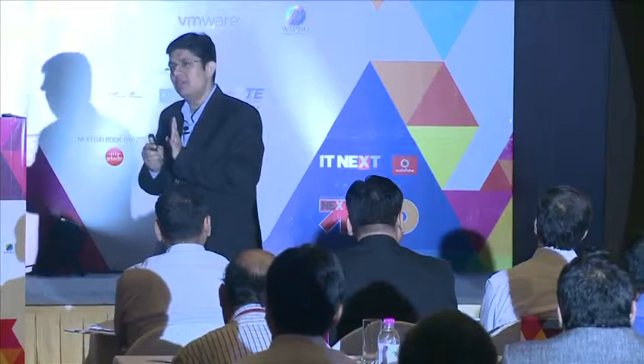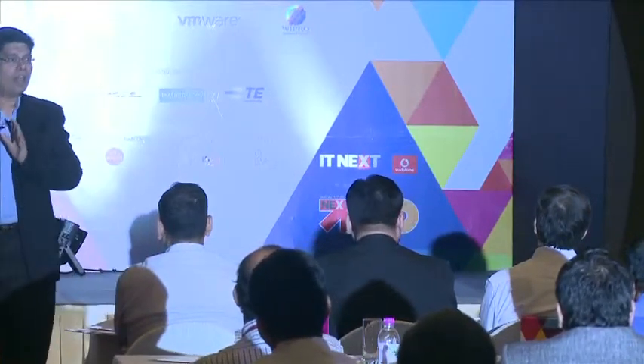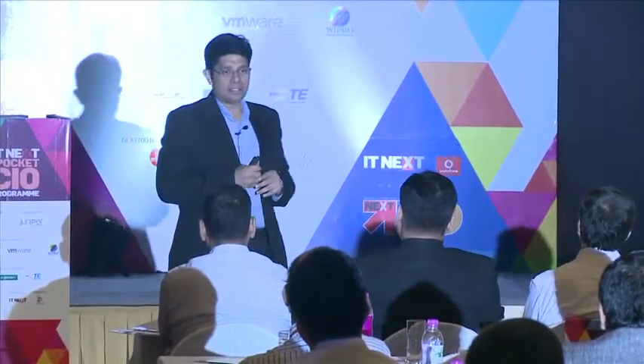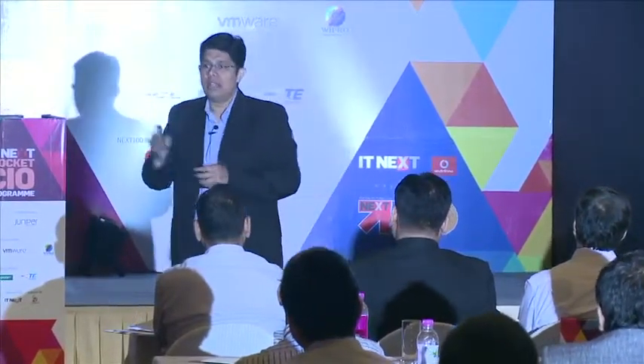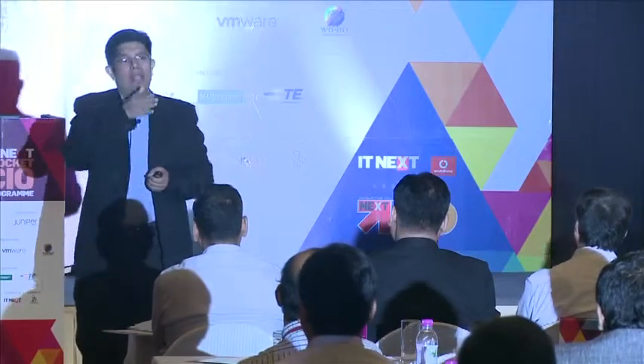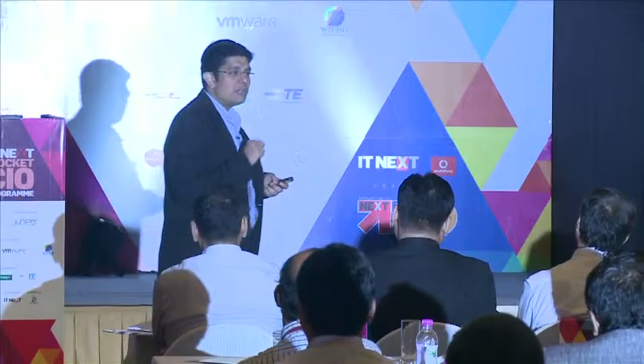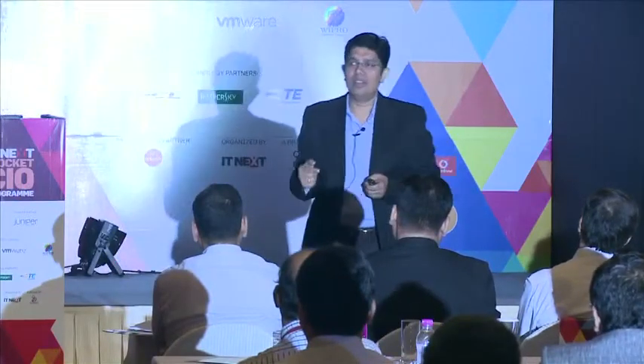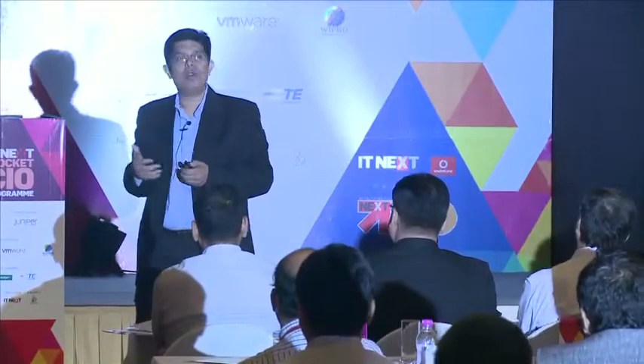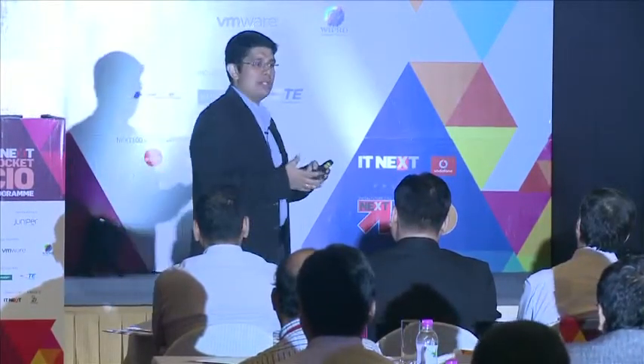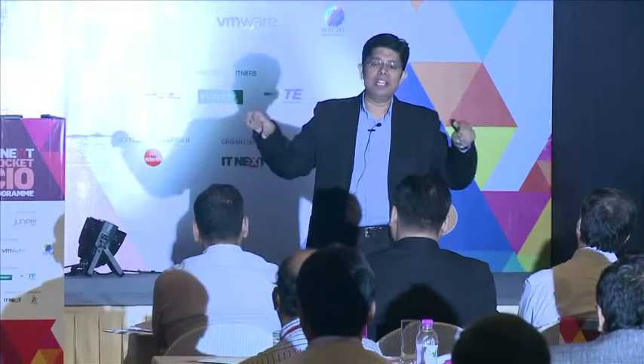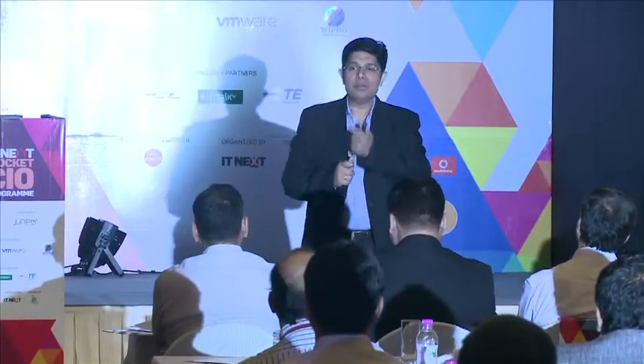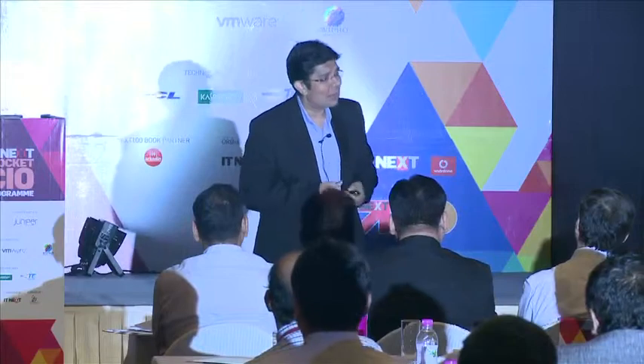When you talk about tier 1 to 4, tier 4 is highest availability or fault tolerant, and tier 1 is just a single system, with tier 2 and tier 3 in between. As you go from tier 1 to tier 4, you increase redundancy, avoiding single points of failure and making systems more robust, so any calamity impacting the facilities won't affect your data center. That's how you plan for tier 2, 3, or 4 depending on your business requirement and what you want to achieve.